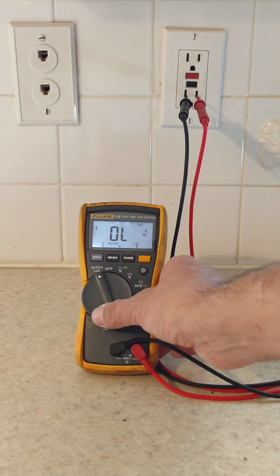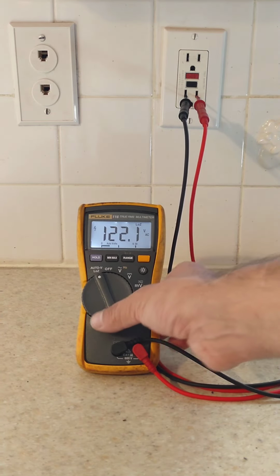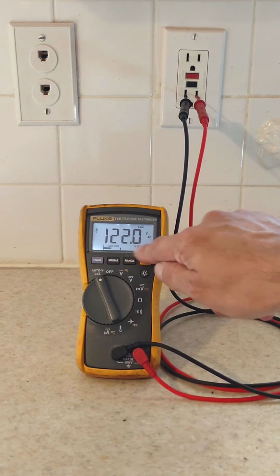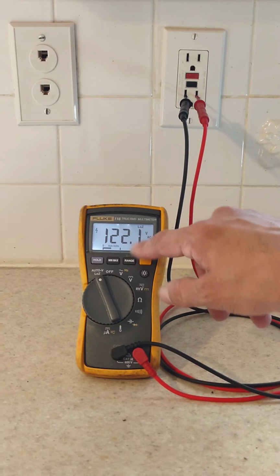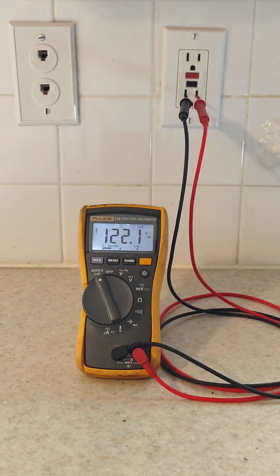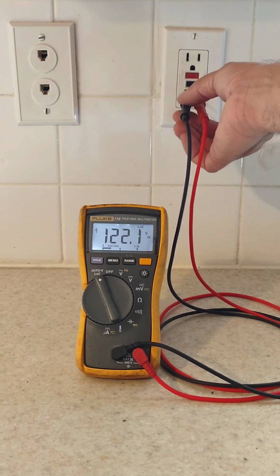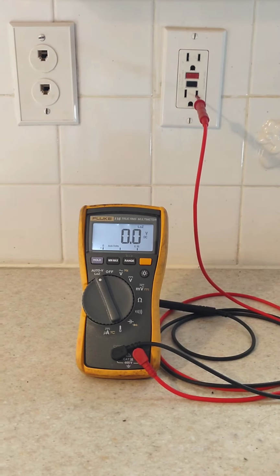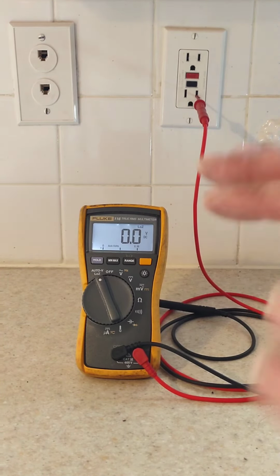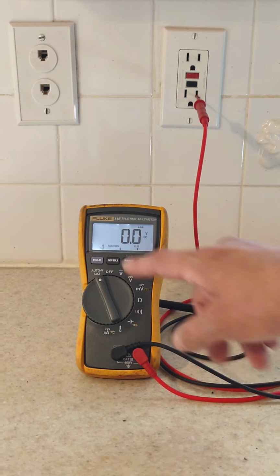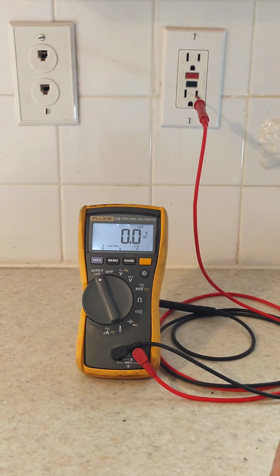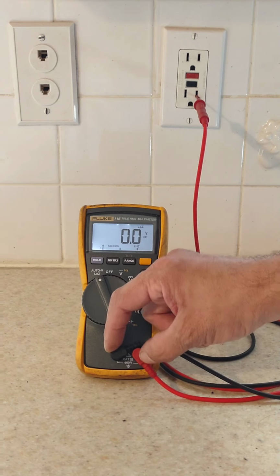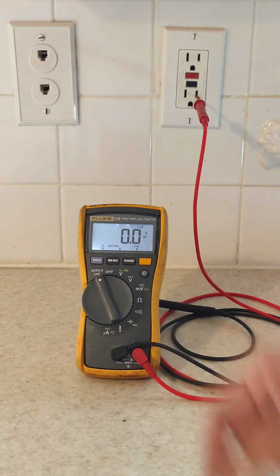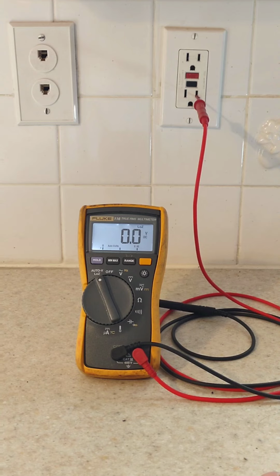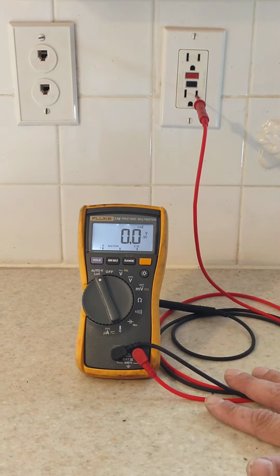So if I clip over to low Z, you can see right now it's showing the same reading, 120 volts. 122 is 120 volts. If I disconnect the neutral lead, it shows 0. It tells us there is nothing usable there. And the only thing the meter has done is it's connected a resistor, connected a load between these two terminals. I think it's about 700 ohms or so, which pulls down that ghost voltage.